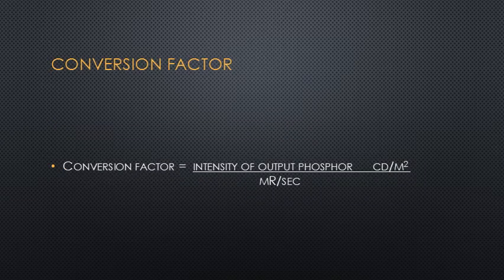The output phosphor is measured in candela per meter squared, which is the measurement of luminous intensity. The higher the conversion factor, the more efficient the image intensifier tube is. Conversion factor is the recommended unit of measure by the International Commission on Radiation Units and Measurements — this is how you quantify image intensifier brightness gain. Typical values are about 80 to 250 candela per meter squared per milli-Roentgen per second, or we can think of it as 8,000 to 25,000 times.